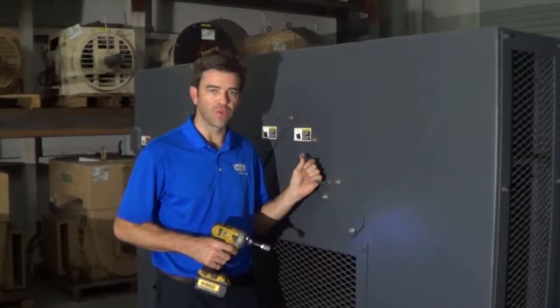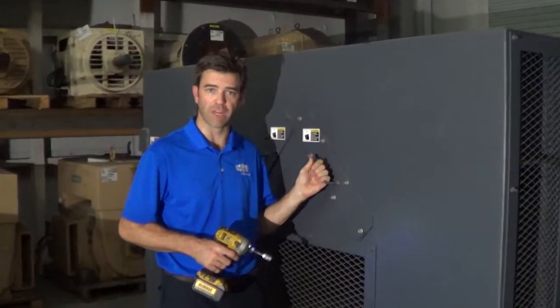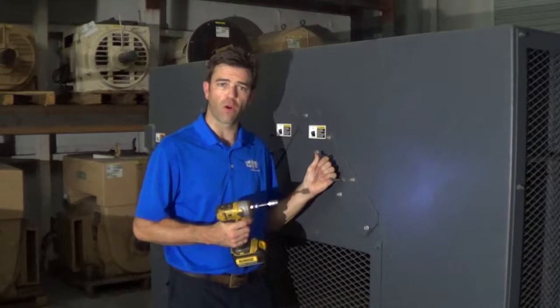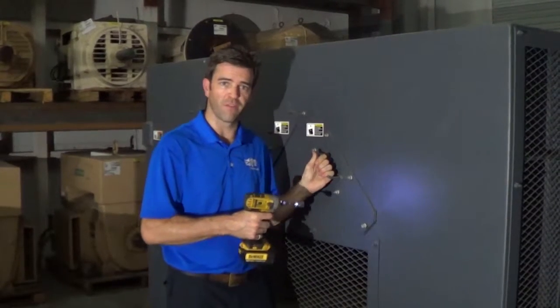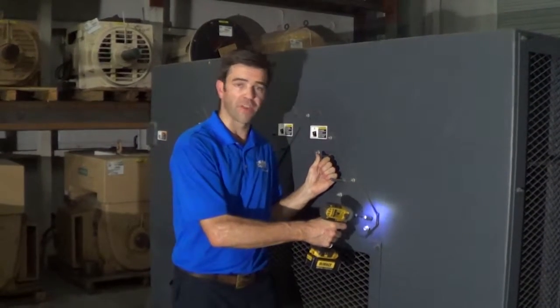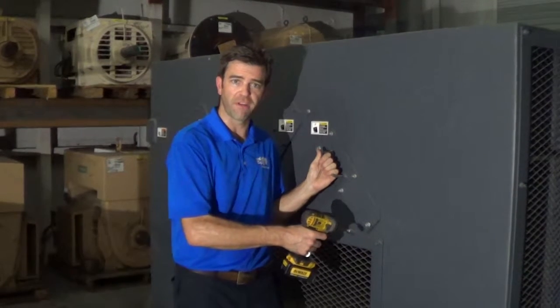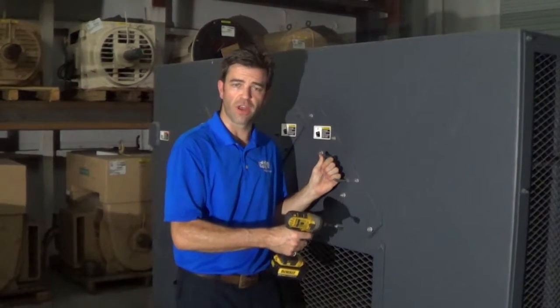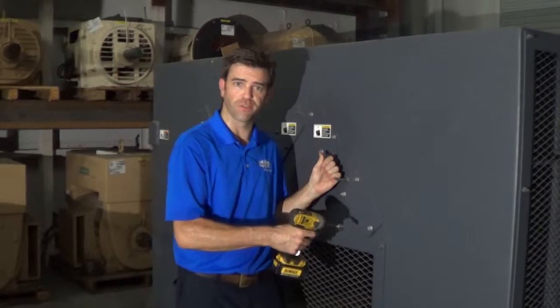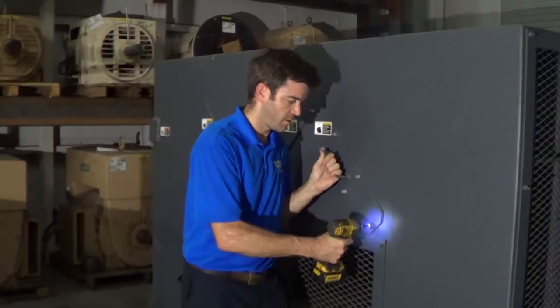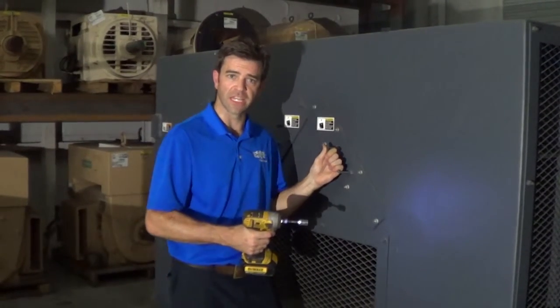It's always preferred to use hand tools when installing and removing covers, but if you're going to use power tools, don't hammer on the fastener, as this will damage both the gasket material and the threaded fastener. Simply go until the driver clicks, and then use a hand tool to finish up. That's sufficient to tighten this panel cover.